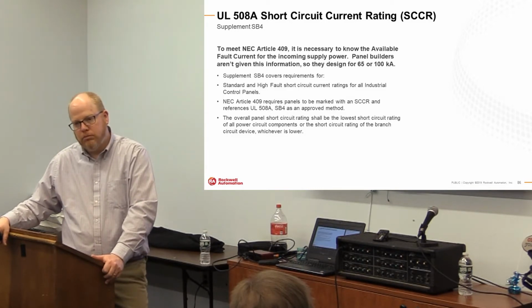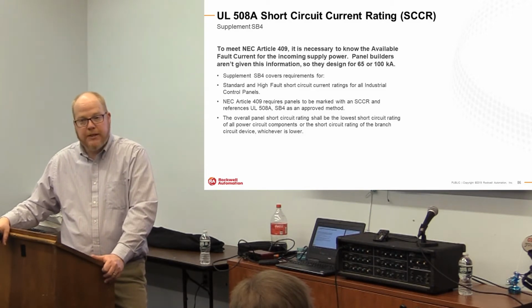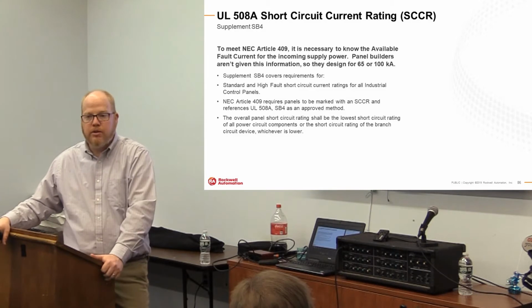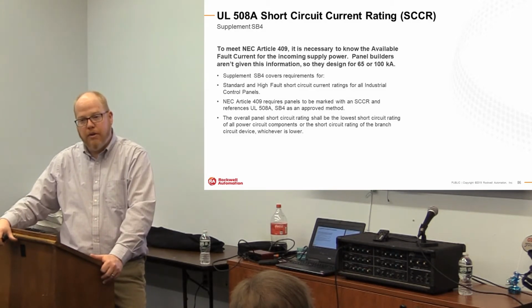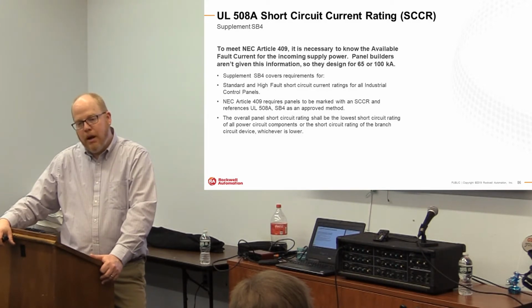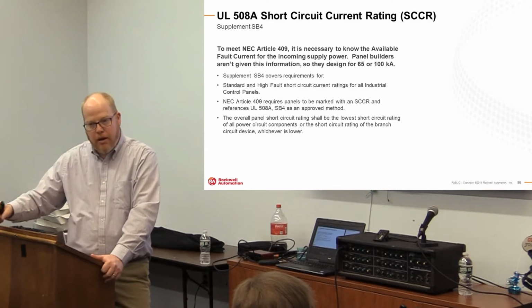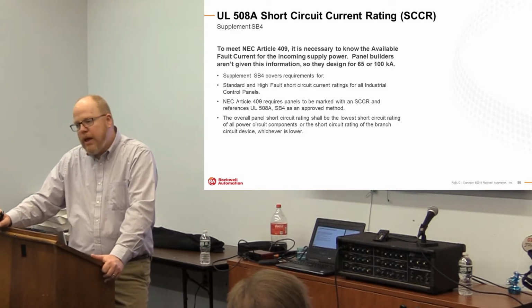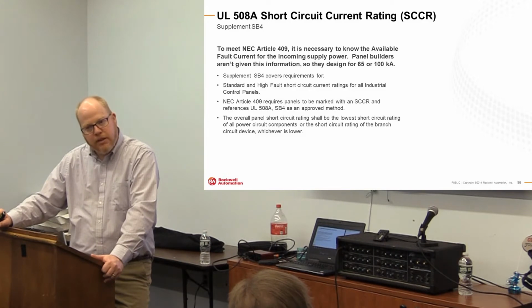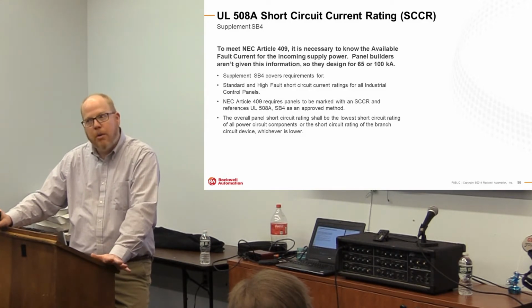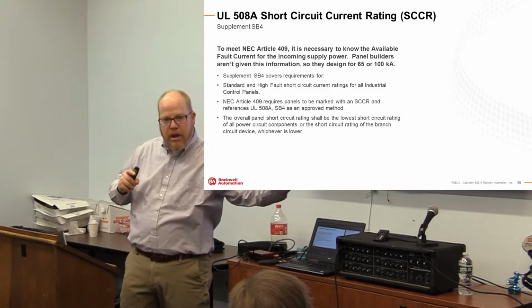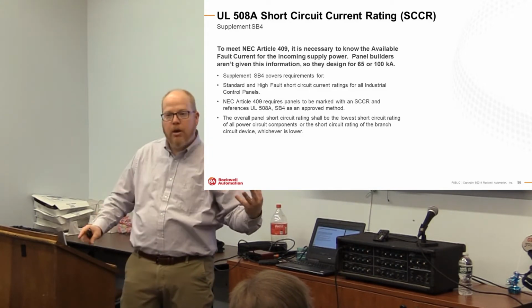So you do the calculation based on the assumed 65? Yeah, based on a target. Yes. So you're saying my target is 65. Well, I know what the customer's going to do with that. Absolutely nothing. Correct. But according to the NEC, they'll just say, oh, there's a sticker. Yeah. But according to the NEC now, and back into that Article 409, they are required to base their installation on a real calculation. So somewhere in the regulatory chain, they are supposed to do a true fault calculation.